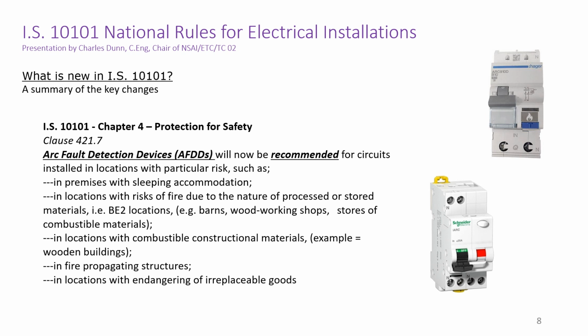Okay, now we get to the real game changer. In Chapter 4, Protection for Safety, Clause 421.7 introduces AFDDs, arc fault detection devices. AFDDs monitor the circuit for arc faults caused by breakdown of insulation or failing contacts or even poor terminations. Arc faults are a known cause of fire.